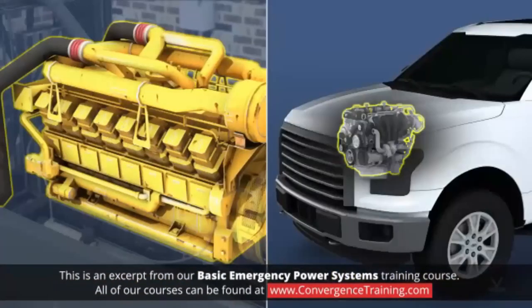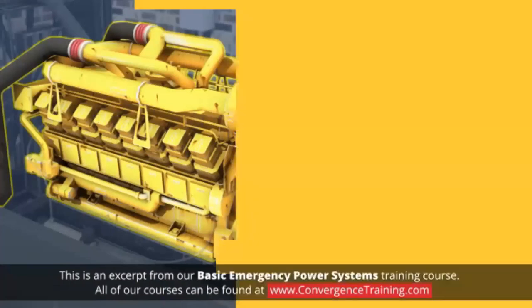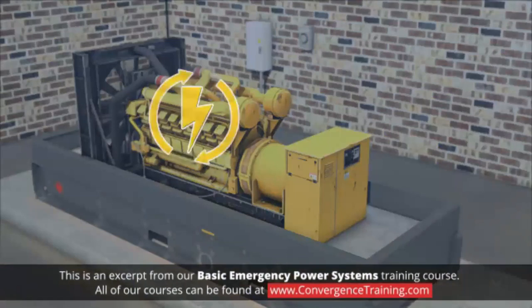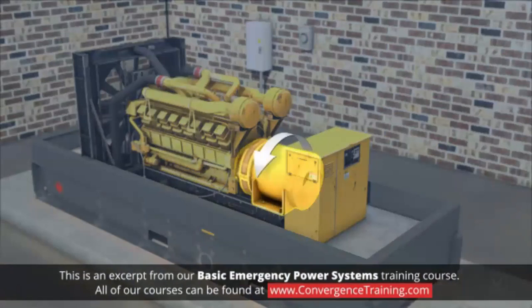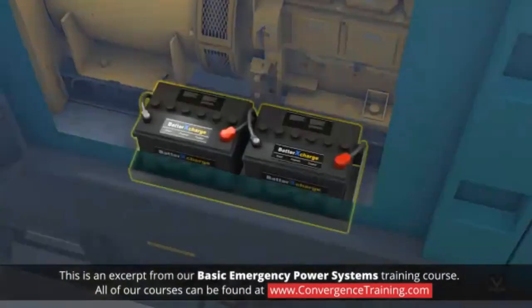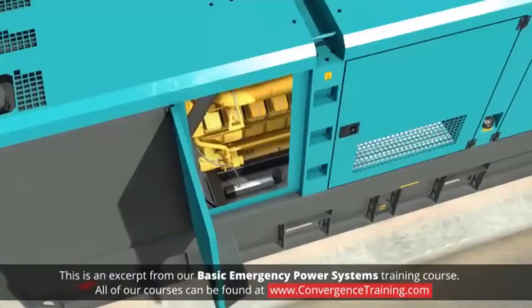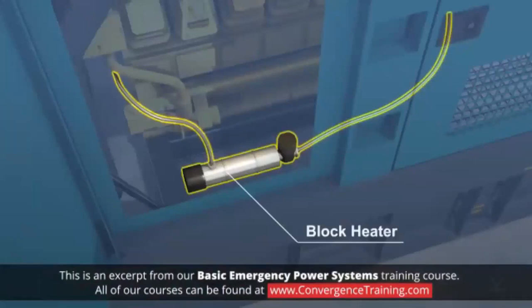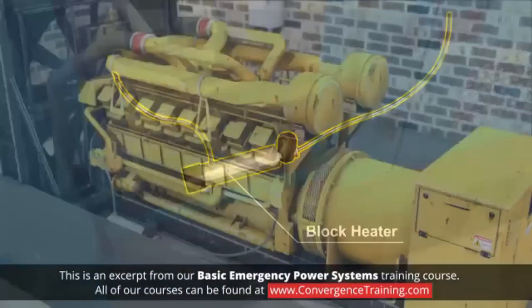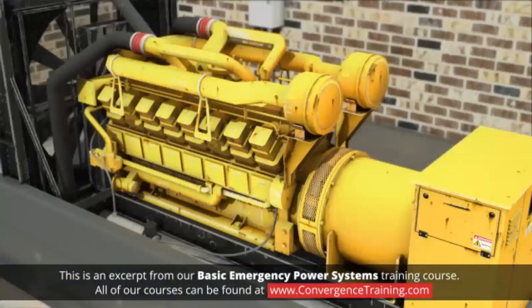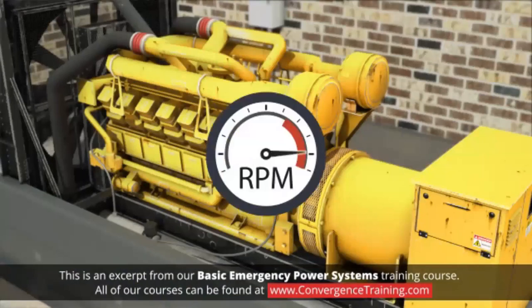The internal combustion engines used in generators are very similar to the engines used in your car or truck, with just a couple of modifications. Those modifications allow the generator engine to start up very quickly and to run at a fixed speed for many hours or days without undue wear and tear on the engine. Like most internal combustion engines, generator engines are normally started by using a lead-acid storage battery. Almost all generator engines are designed to use what is known as block heaters, which must be connected and kept operational all the time, especially when the generator is in a standby mode, not running. Block heaters are powered by normal line power. If the block heater doesn't run all the time, there is a good possibility, particularly in colder climates, that the engine lifespan would be shortened considerably, as it must come up to full RPMs as soon as it is started.